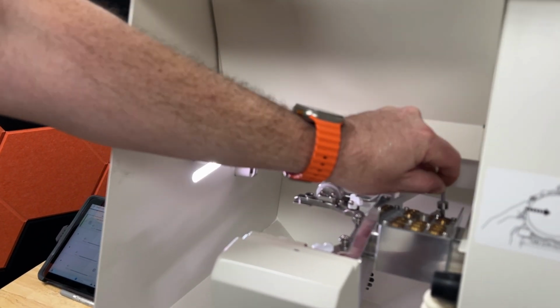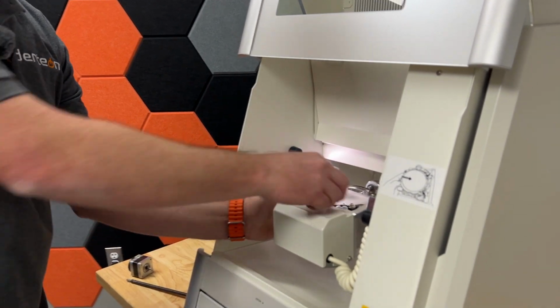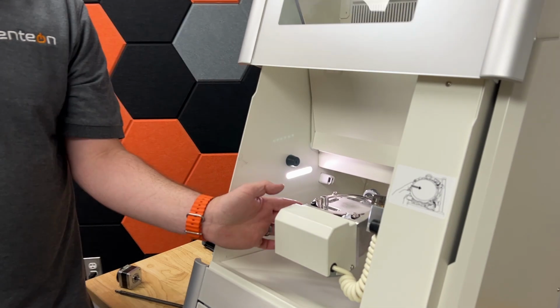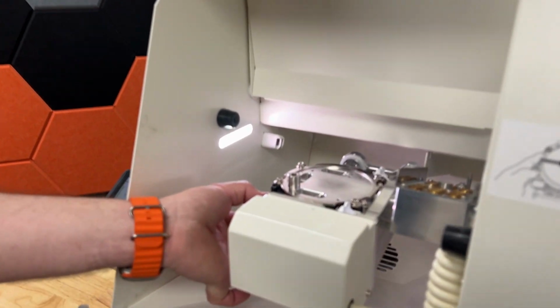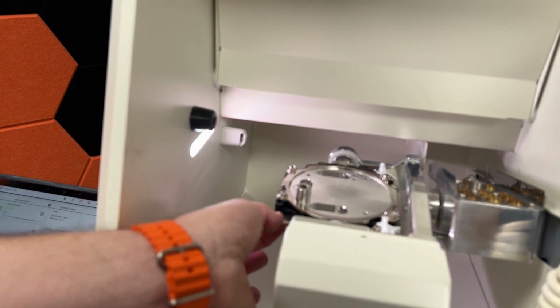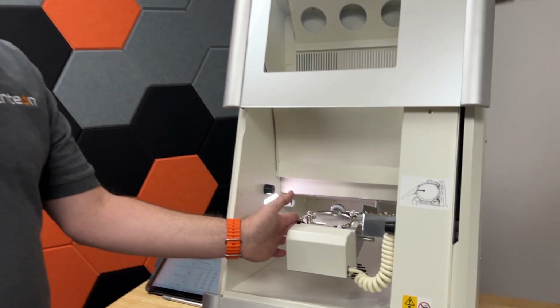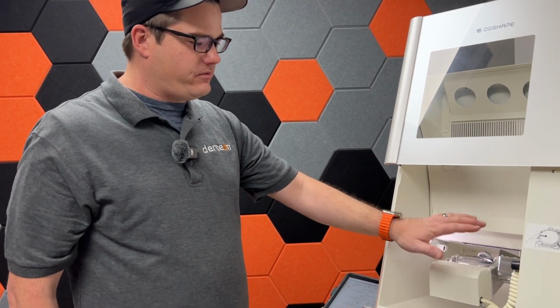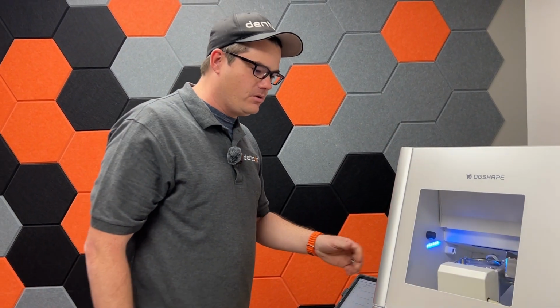Once you've satisfied all of those requirements, we can put our pin where it goes. We can load the calibration disc, click it in, and then we're going to do the wiggle test. I'll explain the wiggle test to you real quick. Wiggle test is we're going to grab the calibration disc right here, and we're just going to give it a little wiggle. And if you can detect any free movement, then you need to stop. If this thing can move relative to the machine, you have a problem, and now you're going to calibrate based on erroneous position. So always do the wiggle test. If it passes the wiggle test, everything's beautiful and clean. Then we shut the door and we move to V-panel.